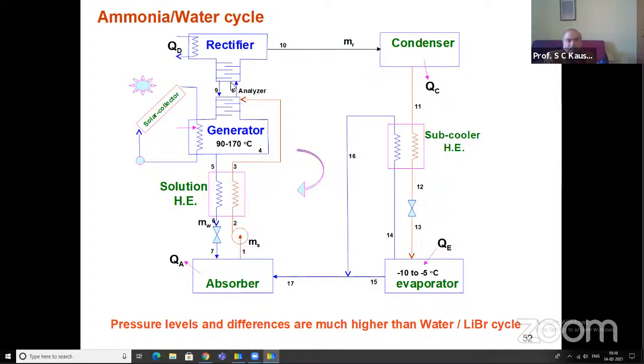Even with a perfect design of the rectifier or this fractionating distillation column, which is known as the analyzer, it is not 100% possible to separate the water vapor from the ammonia vapor. Even 1% or 1.5% or 0.5% water vapors are always associated with the ammonia vapors. So we cannot have a 100% concentration of the refrigerant, ammonia. We will have 0.99 or 0.98 ammonia concentration. And even with that low water vapor concentration, the condensation and the evaporation processes are not perfect. So the cooling effect in the evaporator is low, and that is why the COP of the ammonia water case is low as compared to the water lithium bromide case.